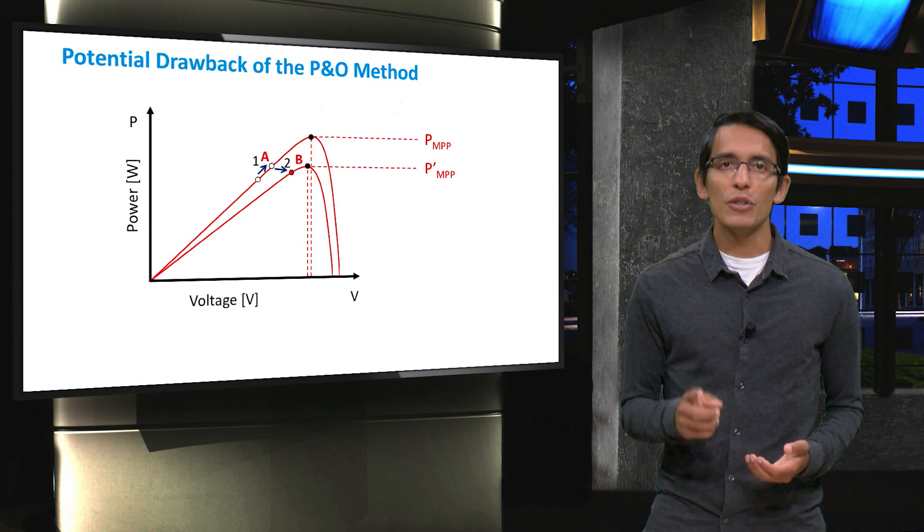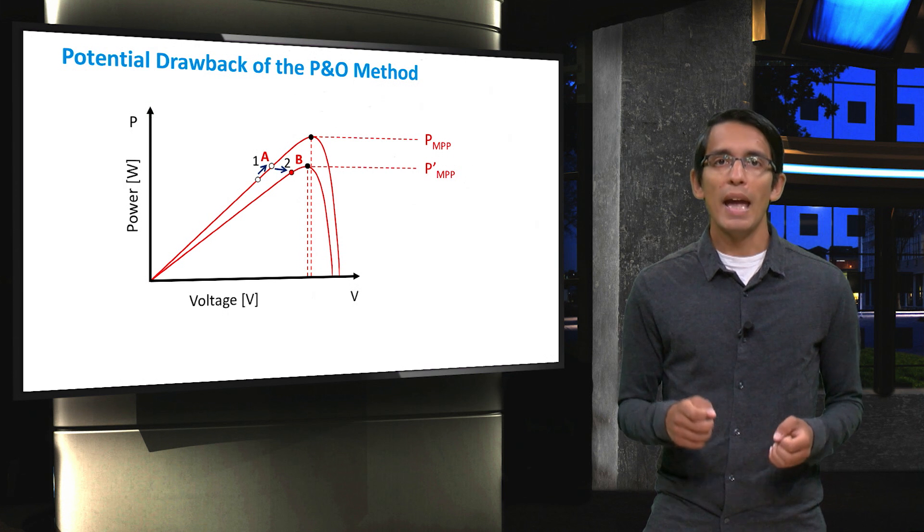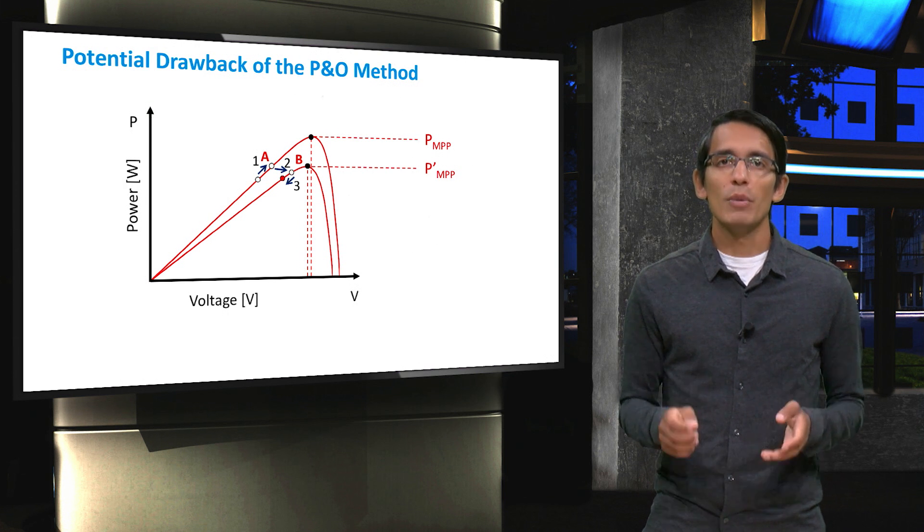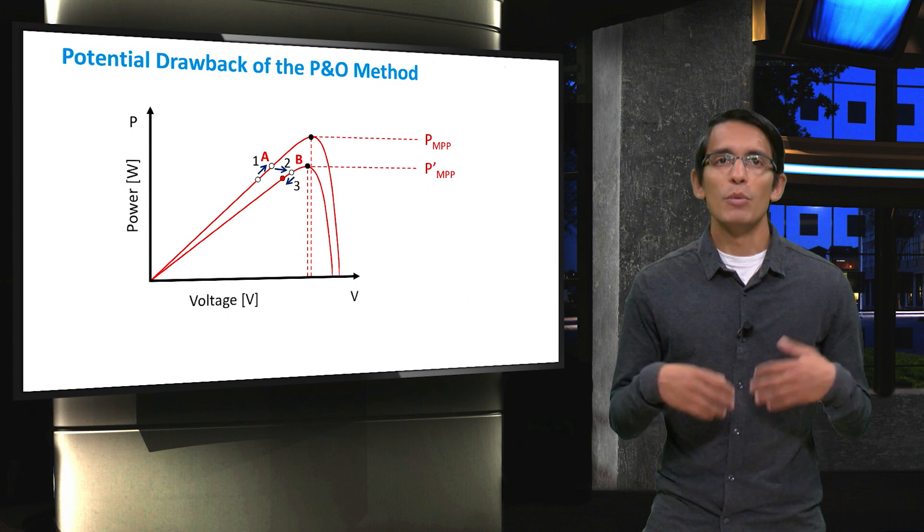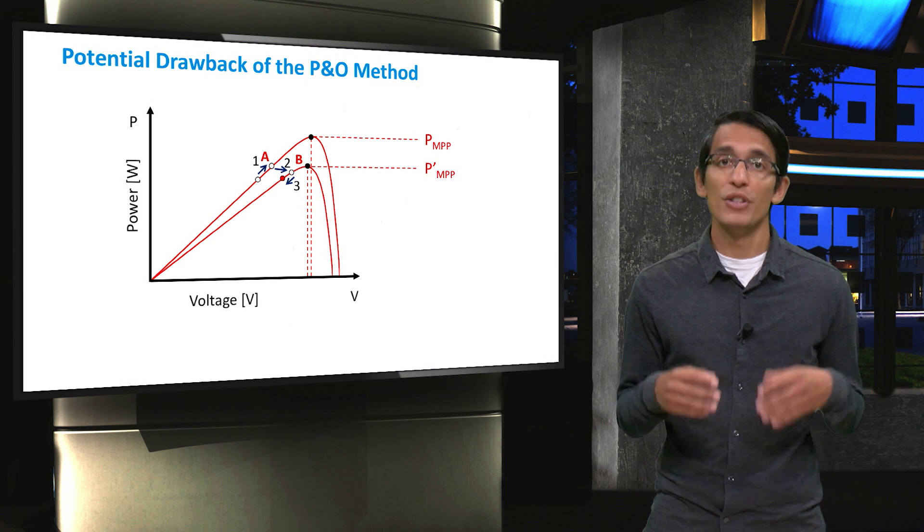Naturally, the system will now assume that the maximum power point is to the left of the current voltage, and so it will move in that direction. The system will eventually correct itself, but if these changes in irradiance are frequent enough, it could result in a PV system operating far from the maximum power point for a significant amount of time.